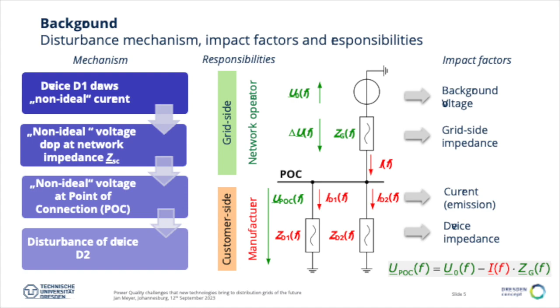What about responsibilities? It's always hand in hand between the network operator and the manufacturers or customers to maintain reliable operation of the grid. It's not only the network operator, nor only the customer — there has to be a compromise between both. Usually the network operator is responsible for the impedance of the network at the point of connection and the background voltage distortion, but this can only be properly managed if the emission introduced by the equipment or customer installations is also limited in a certain way.